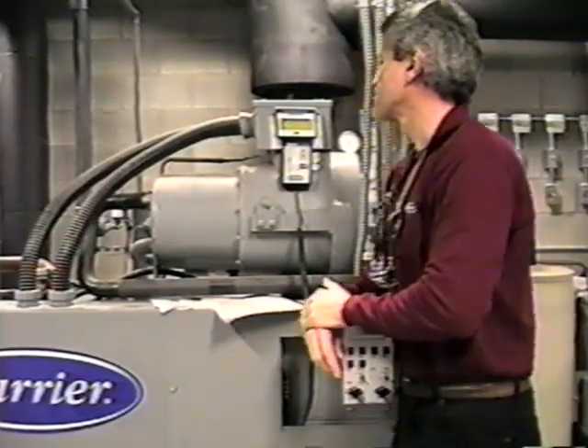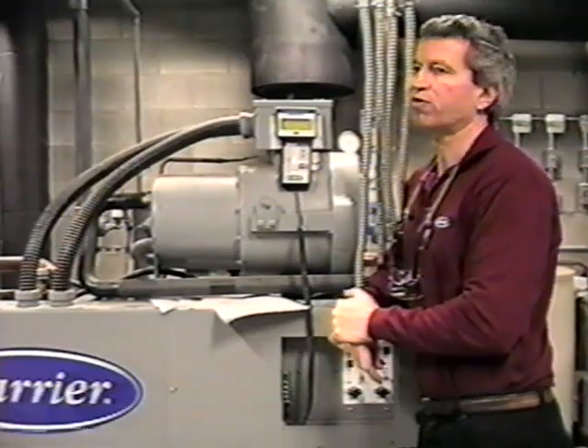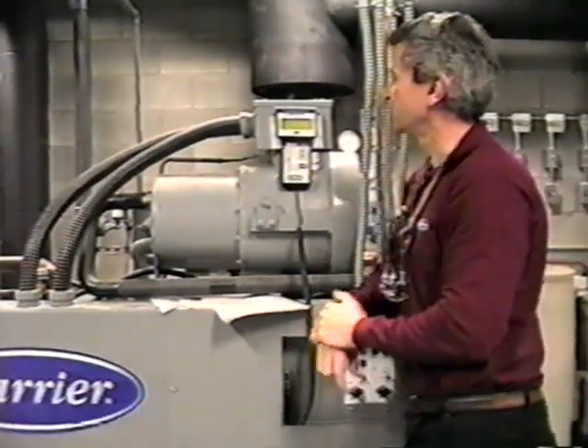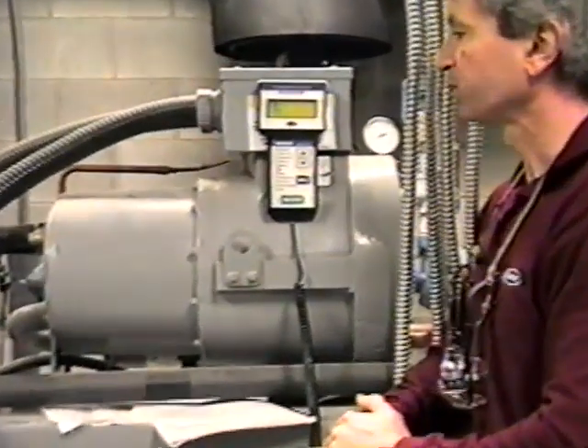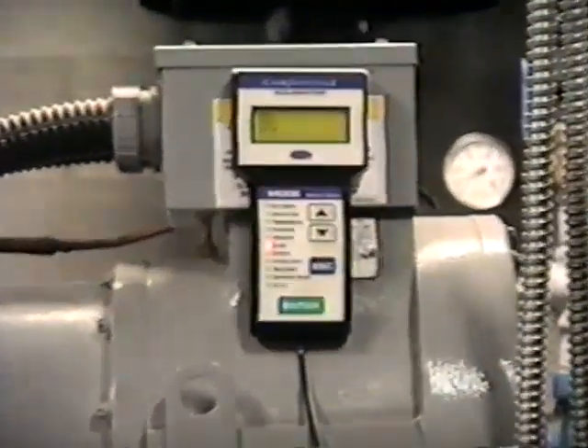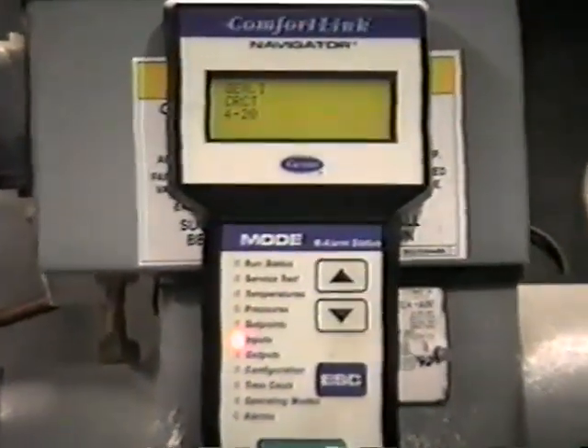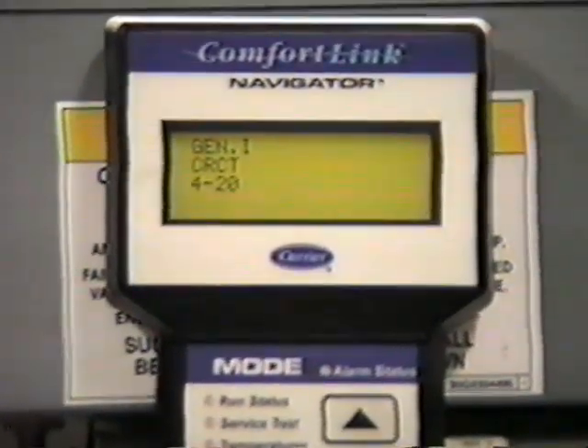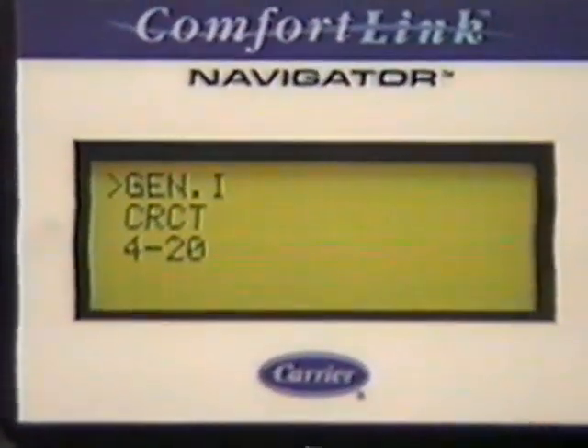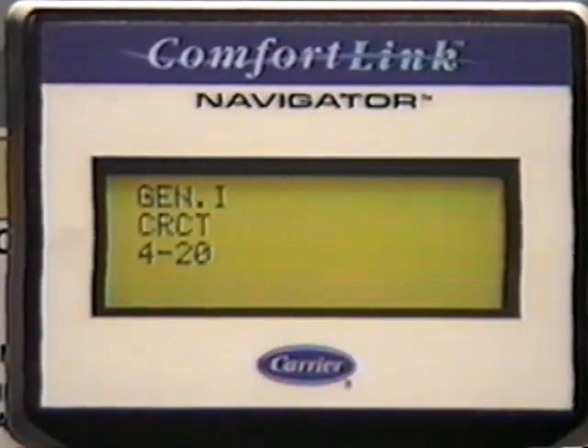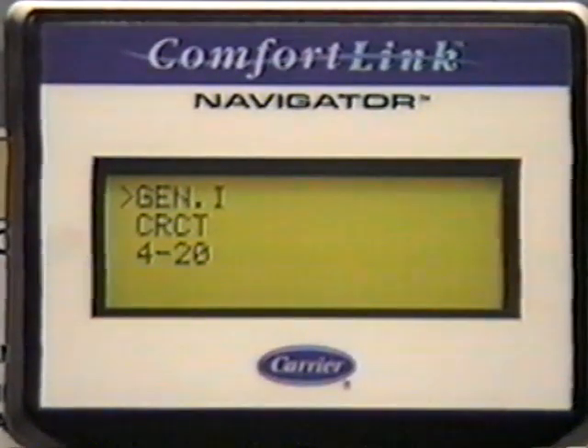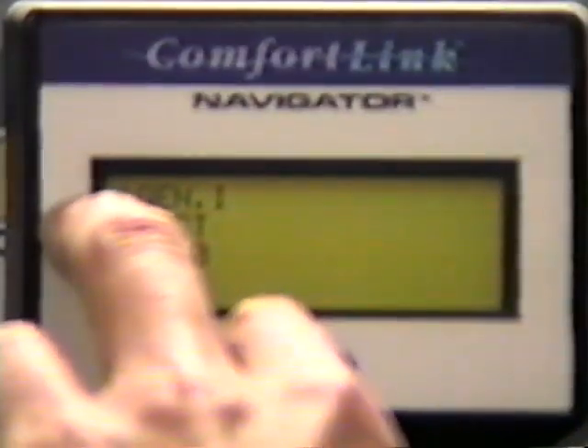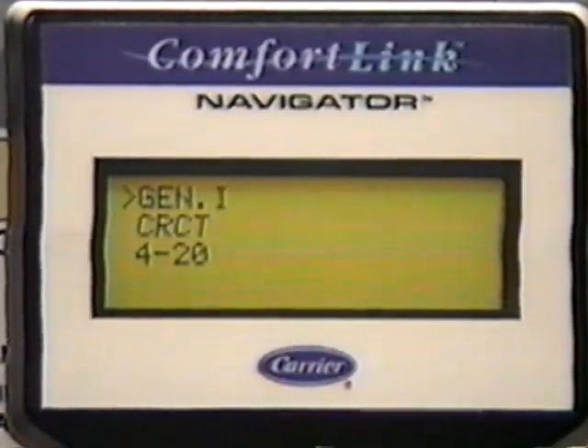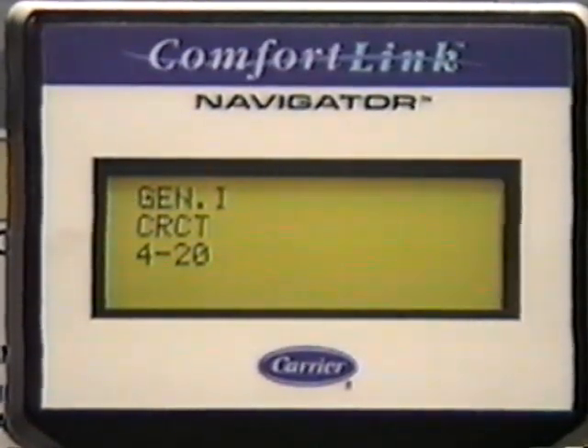The next primary mode is inputs, and that's a listing of all your inputs that are fed back to the processor. Inputs such as the status of your compressor contactor, telling it, yes, the compressor contactor did close and I'm up and running. So things of that nature. You have a general input screen, you have a circuit input screen, and then any 4 to 20 milliamp inputs that may be used for resets or things of that nature.